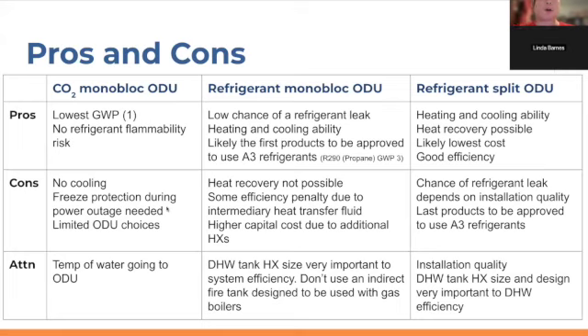So if you need your home to have 4 tons of heating capacity, the way to achieve it is not necessarily to buy a 4 ton outdoor unit in the CO2 monoblock style. You might have to buy like two or three 1.5 ton outdoor units and operate them in parallel in order to get your 4 tons, because there are so limited choices in that category.